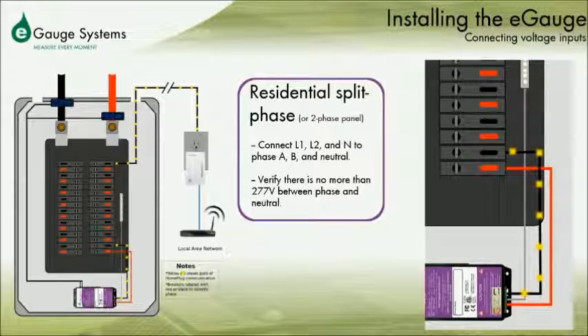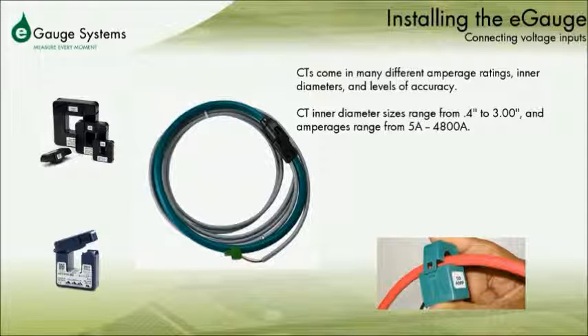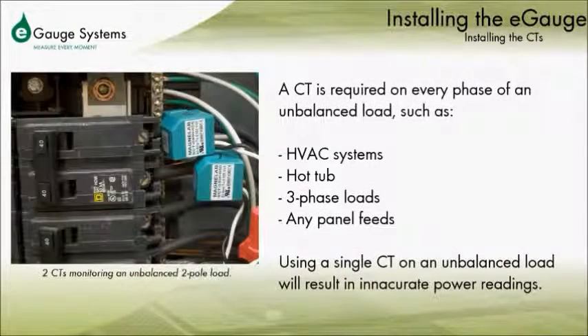After all phases of the electrical system have been successfully wired into the eGauge, you can now begin to install the CTs, short for current transformers. CTs come in many different amperage ratings, inner diameters, and levels of accuracy. Instances that involve non-balanced loads, such as HVAC systems or 3-phase loads, will need a separate CT to monitor each phase of the circuit. This is also the case for electrical systems' main feeds, whether they are 2-phase or 3-phase, as neither instance is a balanced load.